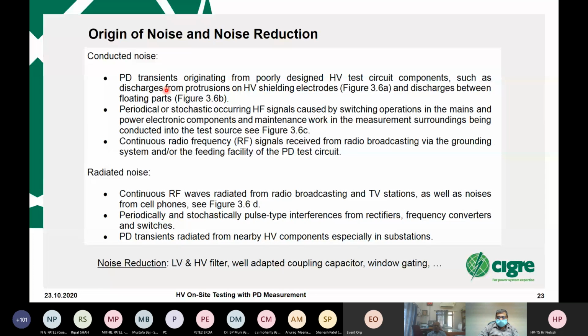The next question is: is this harmful? You have to know what kind of equipment you're investigating - whether it's a special transformer type, how it's built - so you can tell if the issue is on the low voltage or high voltage part. The pattern itself is tricky, and only in very seldom cases can the pattern alone tell you whether it's really harmful or not. The periodicity of the PD signal is also very important.